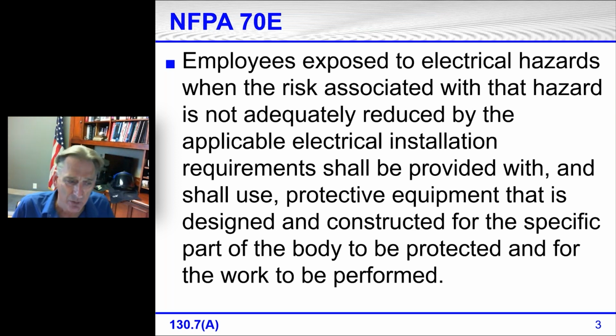70E, in this section 130.7(A), if you'll look in the lower left part of the slide, I give you the reference number where this comes out of 70E. Again, this is all updated to the 2021 edition. Employees exposed to electrical hazards, when the risk associated with the hazard hasn't been adequately reduced by the applicable electrical installation requirements, shall be provided with, and they shall use, protective equipment that is designed and constructed for the specific parts of the body to be protected and for the work to be performed.